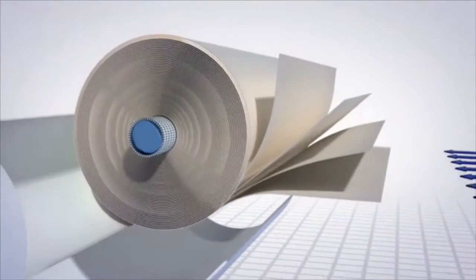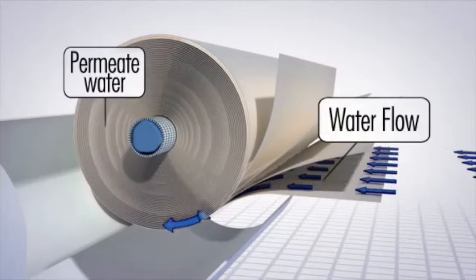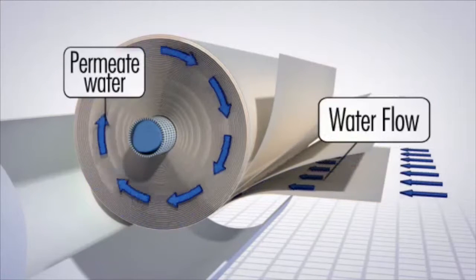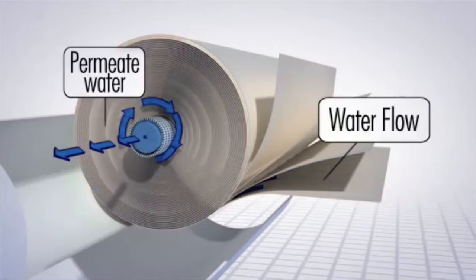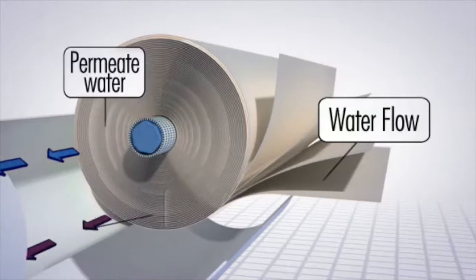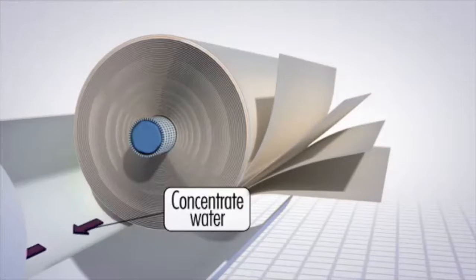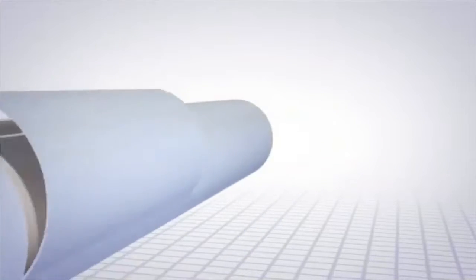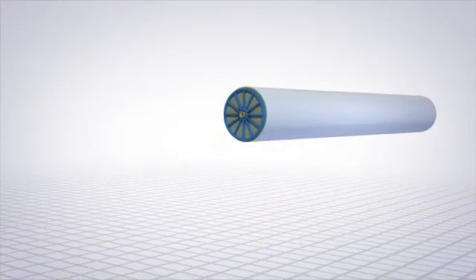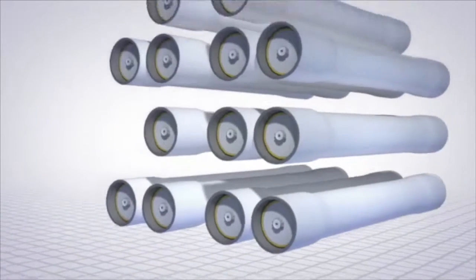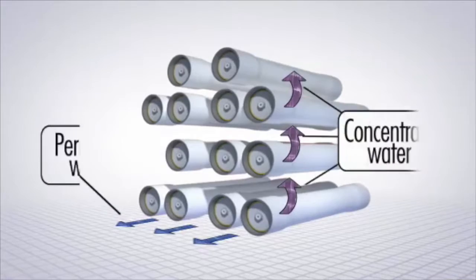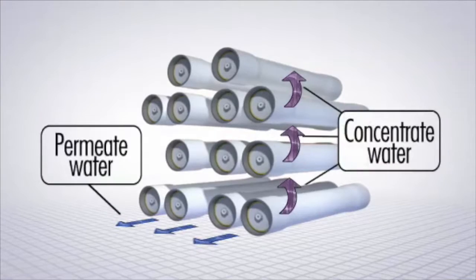Two streams of water are produced. Pure clean water, or permeate, flows across the membrane sheets and passes through the membrane layers to the inside core tube. Water that does not permeate becomes more highly concentrated with salts and other substances. This water is called concentrate. The pure permeate water flows out the core tube at one end of the pressure vessel, and the concentrate water flows out another outlet.